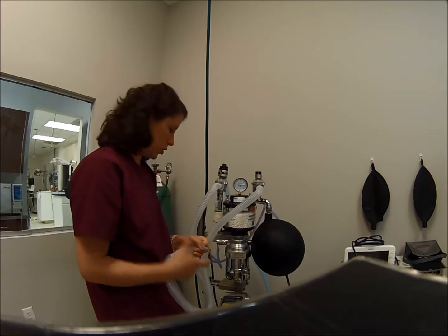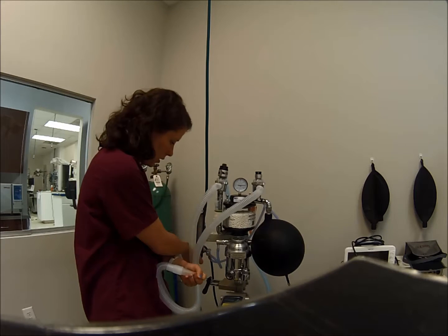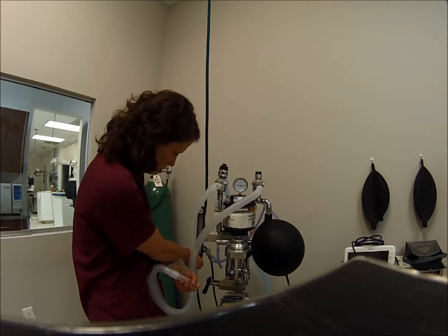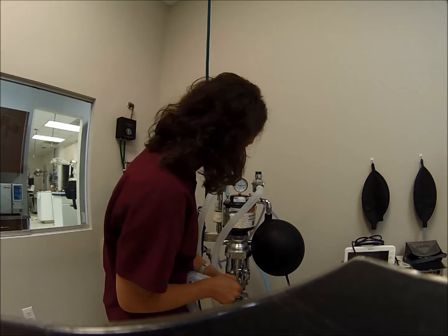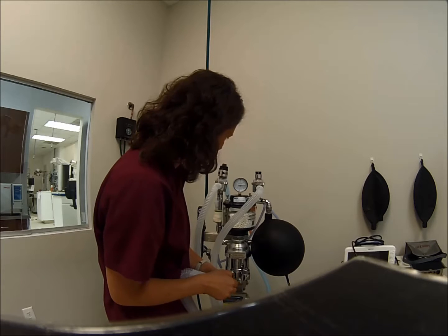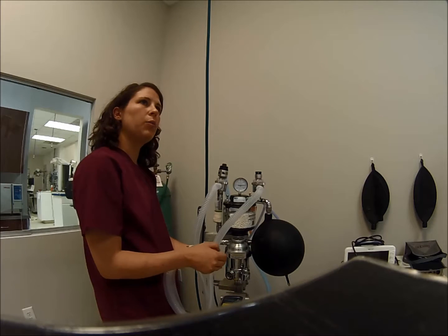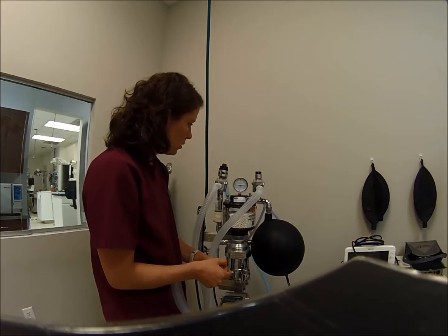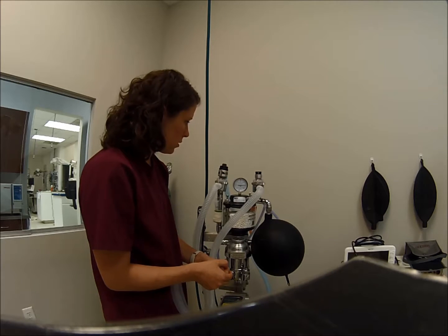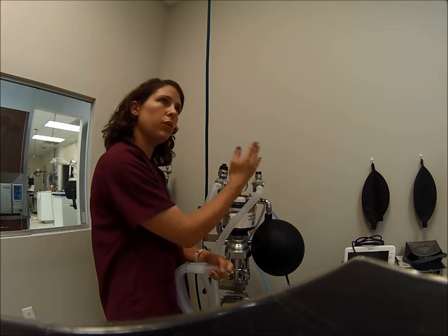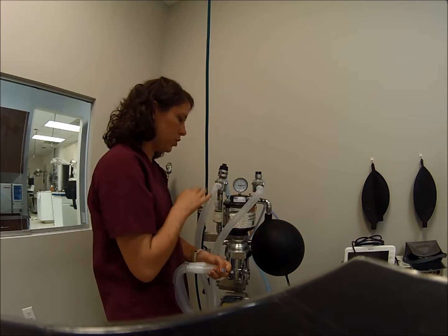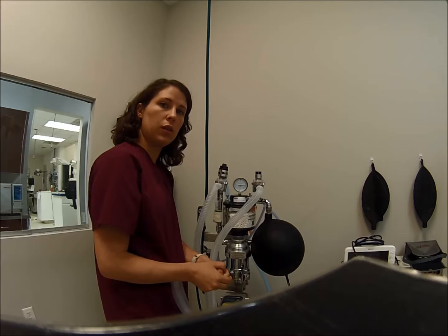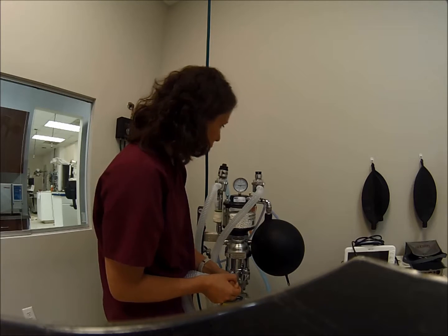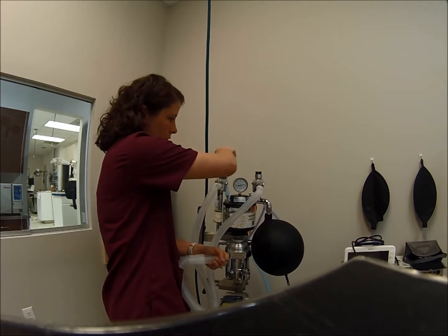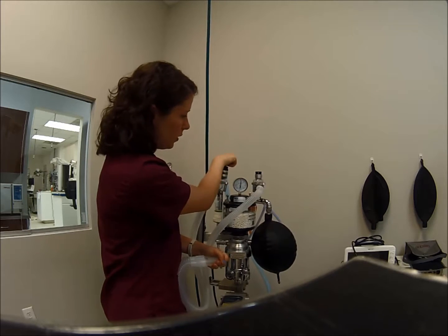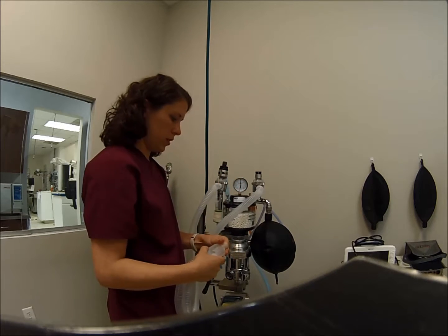What I can do as well to check any leaks in my flow meter is I can turn my oxygen onto 0.2 liters per minute, make sure my needle is not descending. Wait a couple more seconds. If there was a leak, my needle would be moving down towards the 0, and I would have to check each component of the circuit to figure out where the leak is. We look good, so I'm going to go ahead and open my pop-off valve. Now my bag will deflate and my needle will go back to 0 because I'm releasing the oxygen.